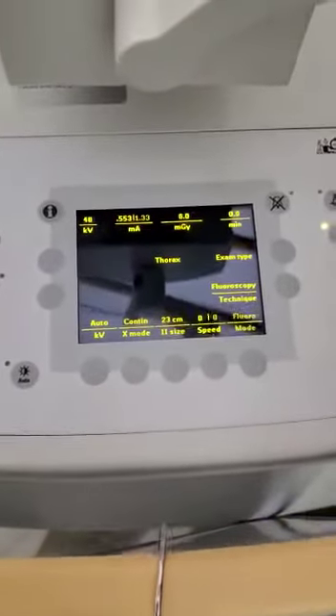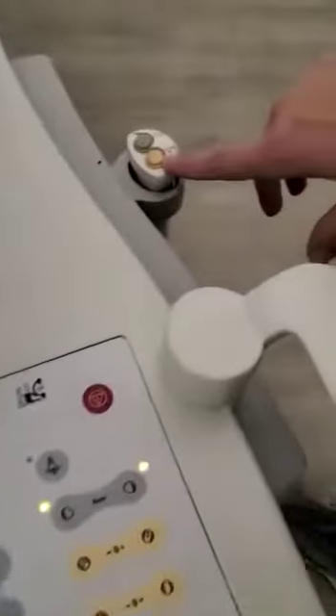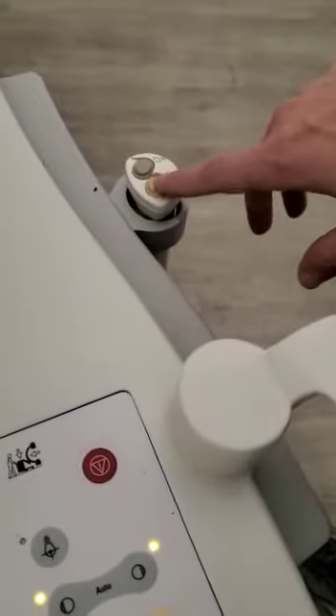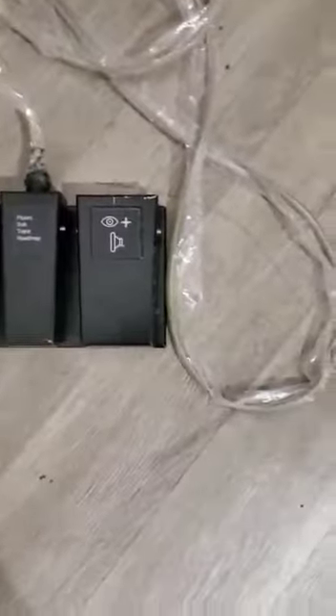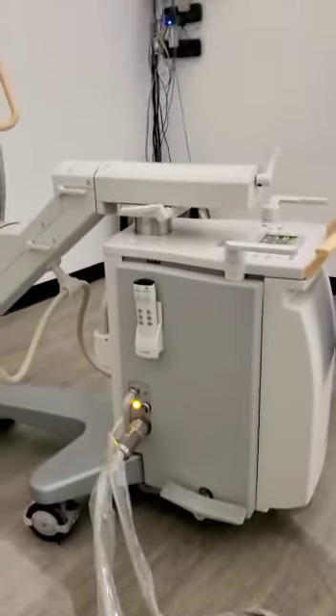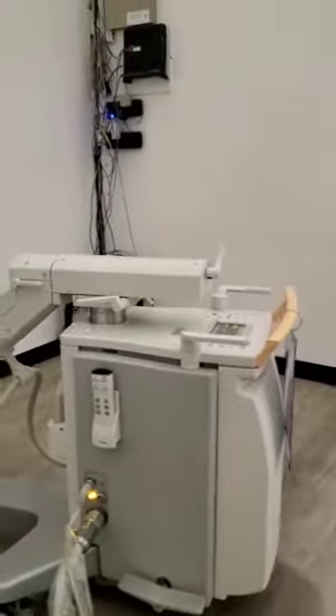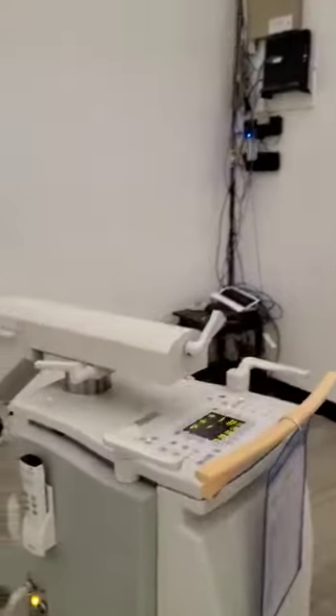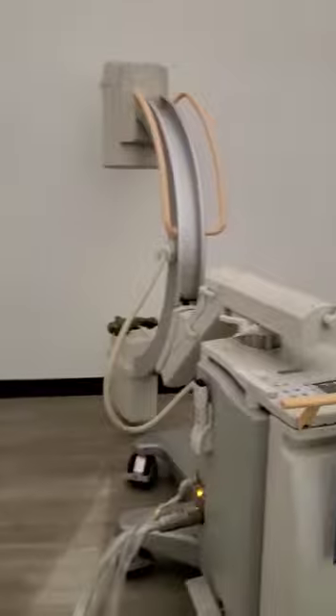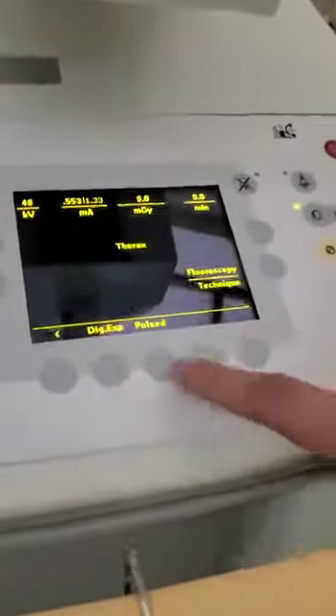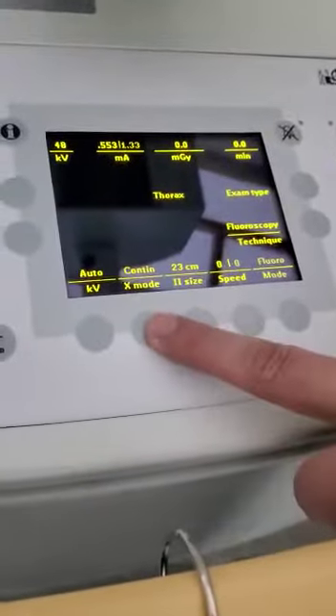So when you hit either the right foot switch, I+, or the right hand switch button, the yellow button, the I+, or your right foot switch, I+, that simply is telling the system, A, to save the image, and B, to release the preset that you've selected on the C-arm. Okay, so now you know how to image or the different fluoro modes. Oh, sorry, let's go over the different fluoro modes real quick. To switch between fluoro modes is done here at the very bottom. X-ray mode.